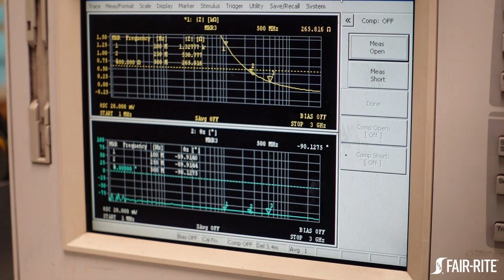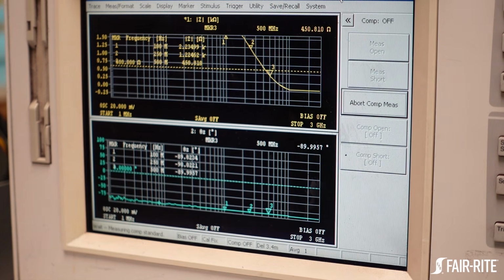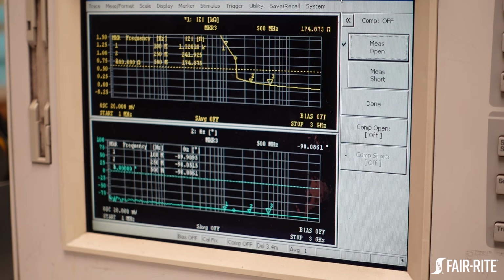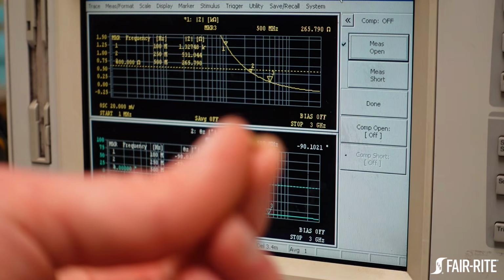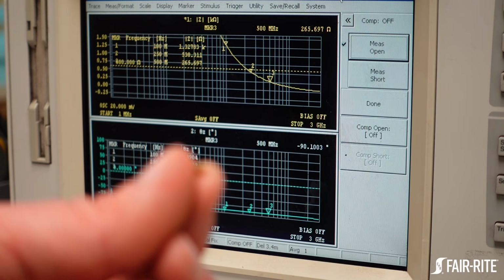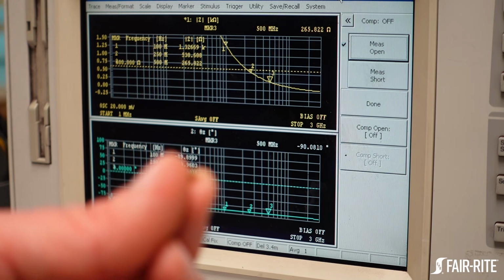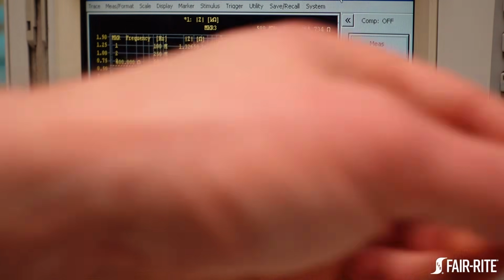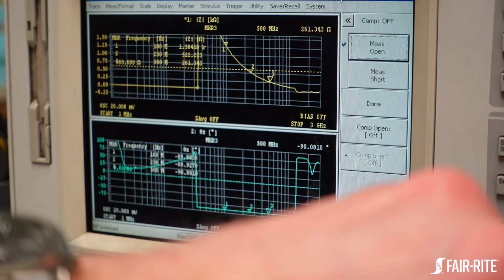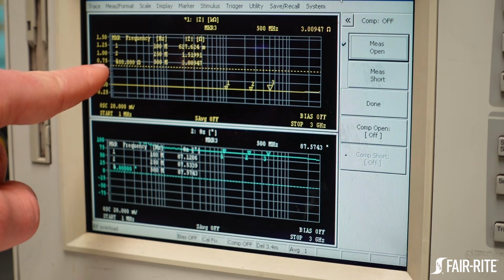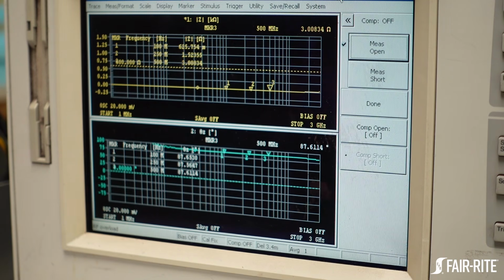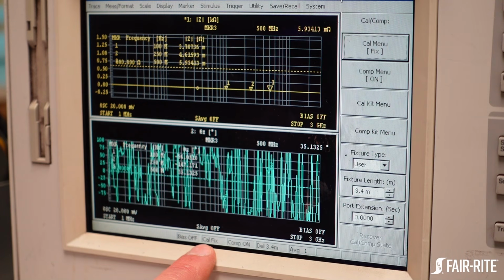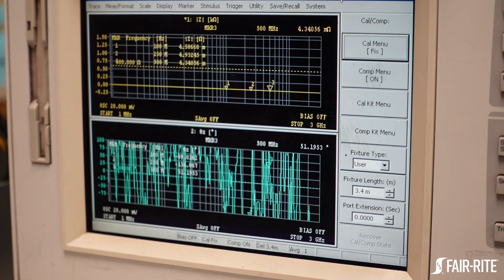So the fixture unloaded, no DUT present. I'm going to hit open. And then we are going to place our gold shorting bar inside the fixture. I don't know that you can see this too well. We're going to place that into our fixture. You can see this drop down to almost 0 ohms. So we're going to hit short. Done. Now on the bottom of our screen it says Cal Fix, compensation on. Now we're ready to measure.